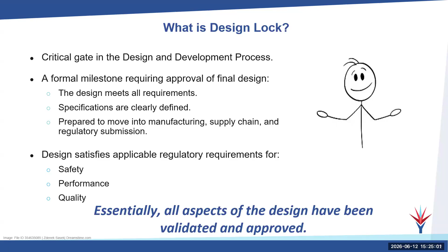Next slide, please. So when should design lock happen? A really important question. Typically, it occurs after design validation is complete and before or during transfer of that design into manufacturing. That's where people get a little fuzzy. Am I done with the testing? Am I really ready to transfer it? Or maybe I want to transfer it and see if it'll work. Or maybe we're almost there, but what we have left to do isn't really that critical. That kind of waffling can really cause you serious problems. You really have to bite the bullet and decide the design validation is complete, and now we're ready to go.